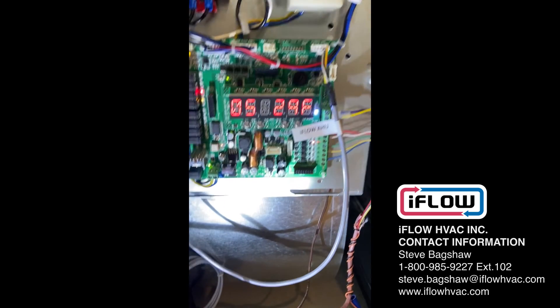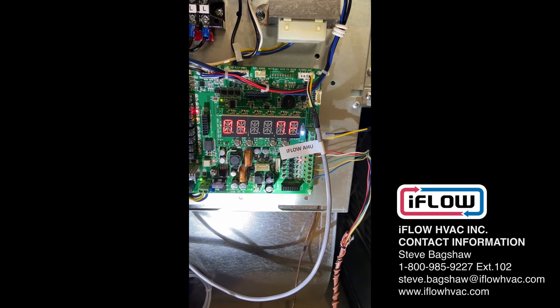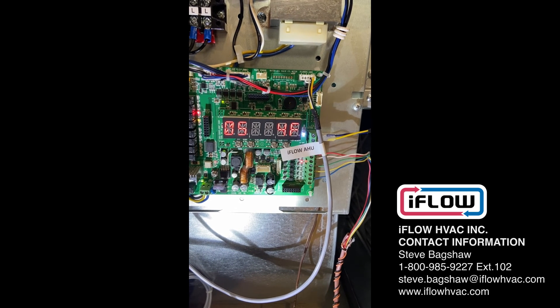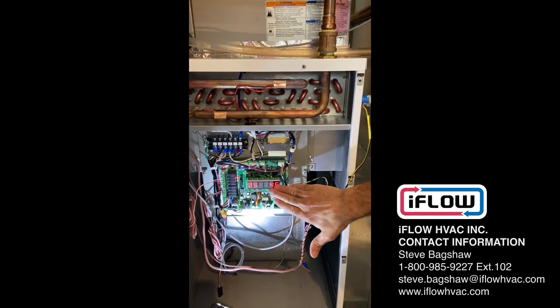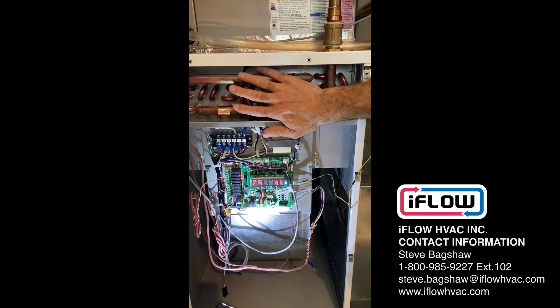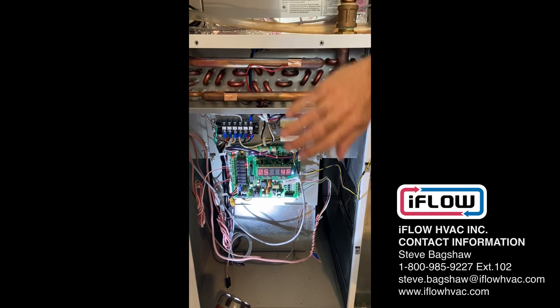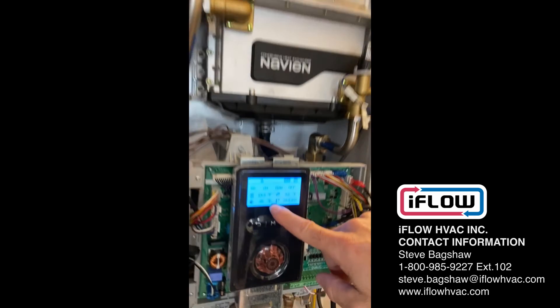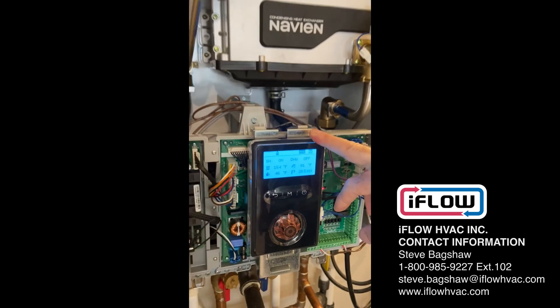Now let's drop this to the maximum — all the way down to zero. You can hear the iFlow is picking up because it's colder outside and we need to deliver more heat into the house. The blower speed is going to pick up, pushing more air across the heat exchanger, taking more BTUs off the coil into the house. And now the Navien is also at 154, and that should jump up soon too.